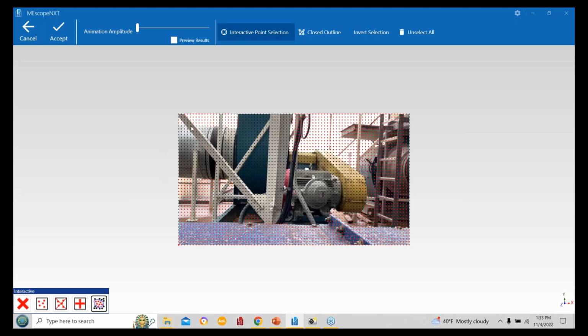So I have the inlet, the fan housing, the bearing cover or the shaft cover right here is a bit of a problem because it's sheet metal and it rattles. Same thing with this. This is a little stiffer made, but it moves. It guards the sheaves. And the motor's moving around. There's a lot of flexure under here that I want to show you.